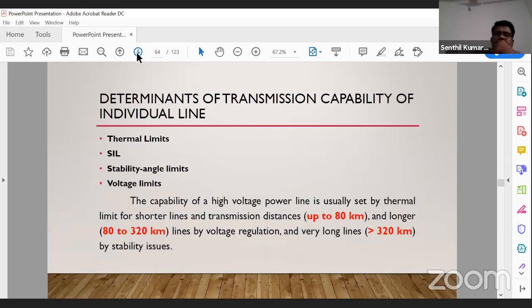And the determinants of the transmission capability of the transmission line are thermal limit and SIL. The capability of the high voltage power line is usually set by the thermal limit for shorter lines and transmission distances up to 80 kilometers.